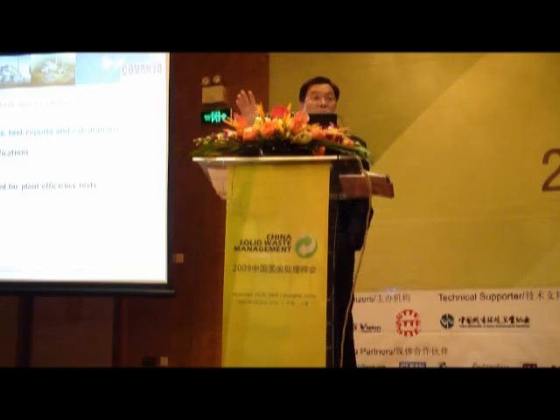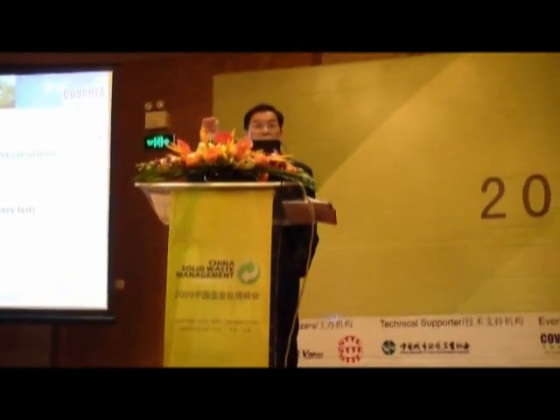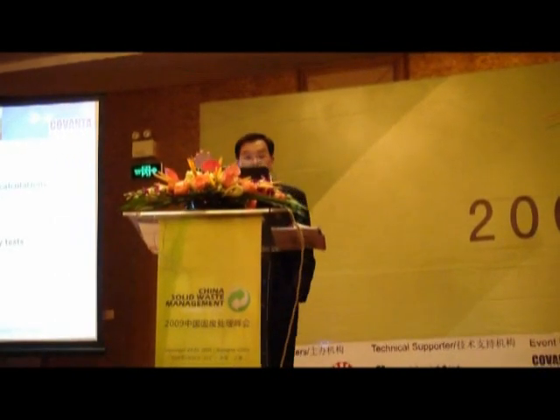Generally speaking, people do not rely on the grab sample to do that heating value measurement. And you do not use bomb calorimeter to measure that. People use the boiler code, which is ASME boiler PTC code 4 or the new one 31. Okay, and then data acquisition system that need to be properly installed.